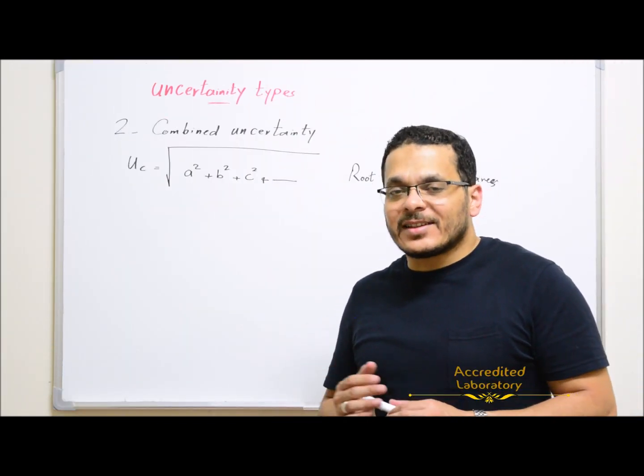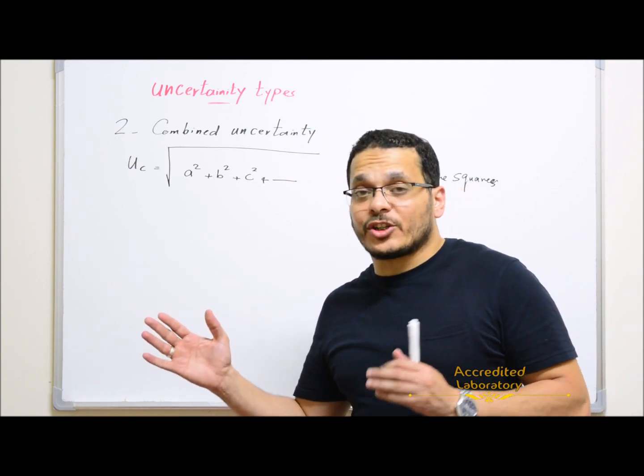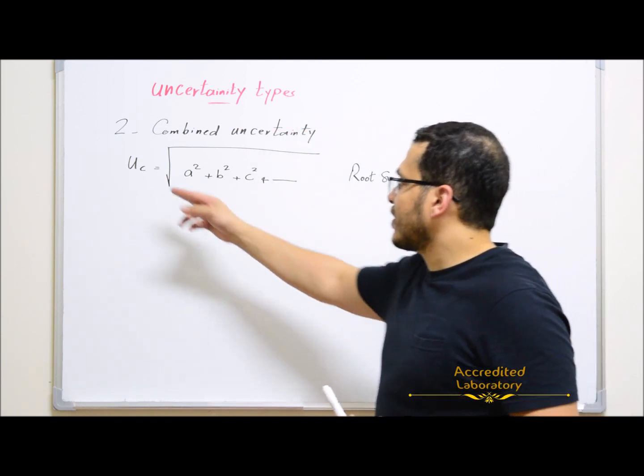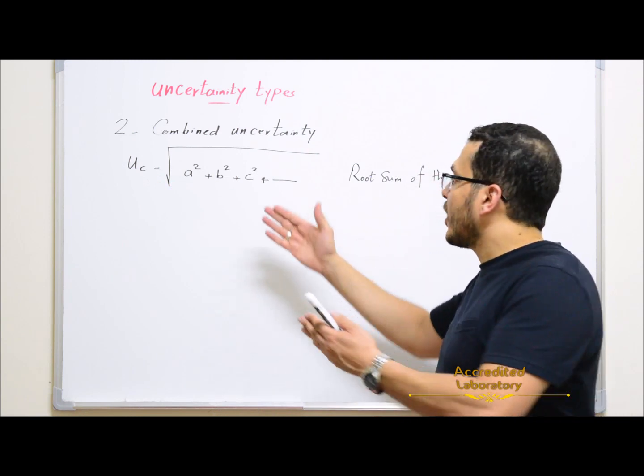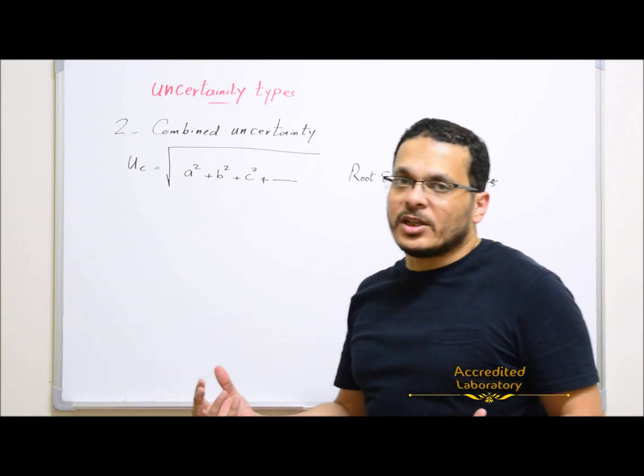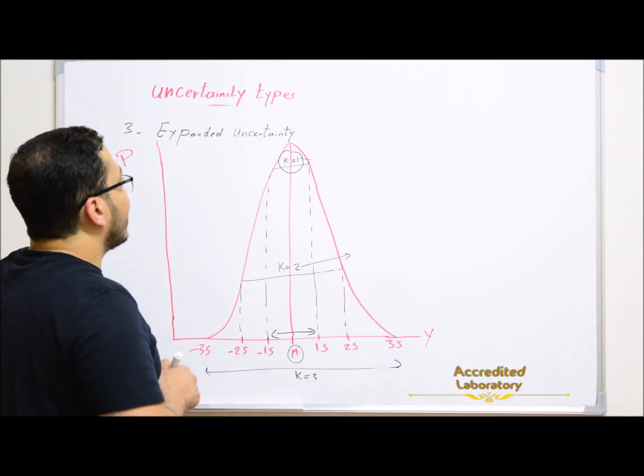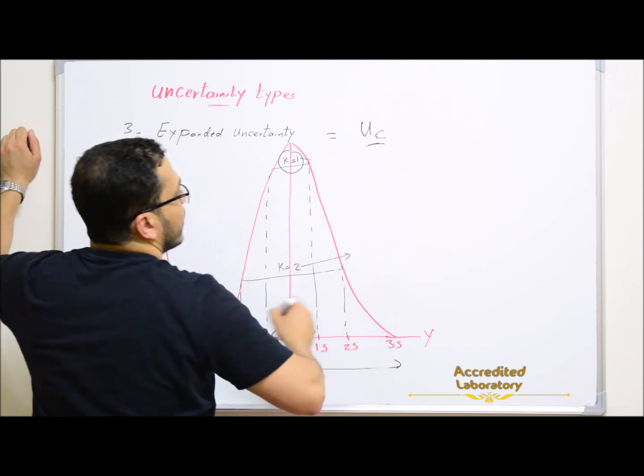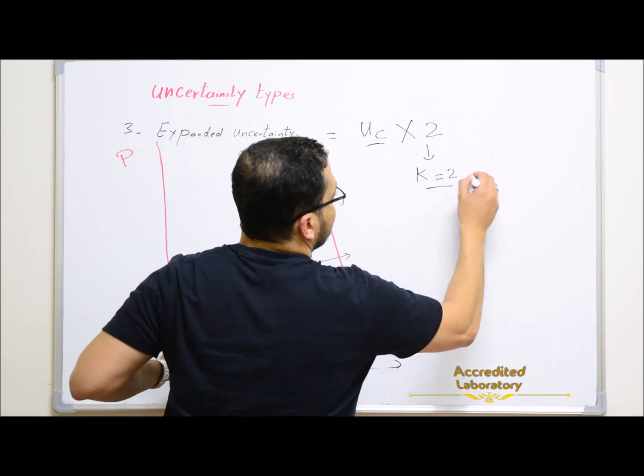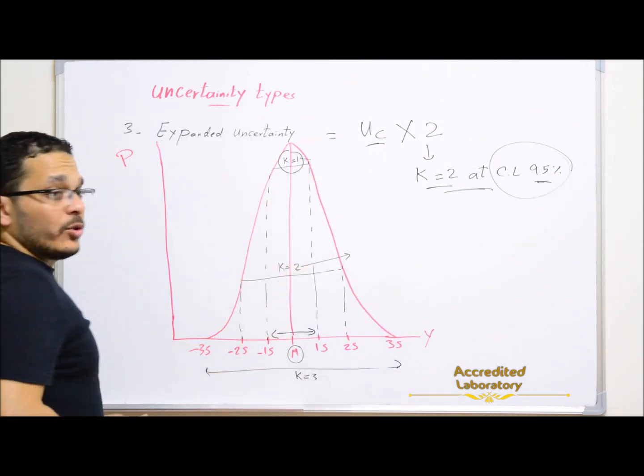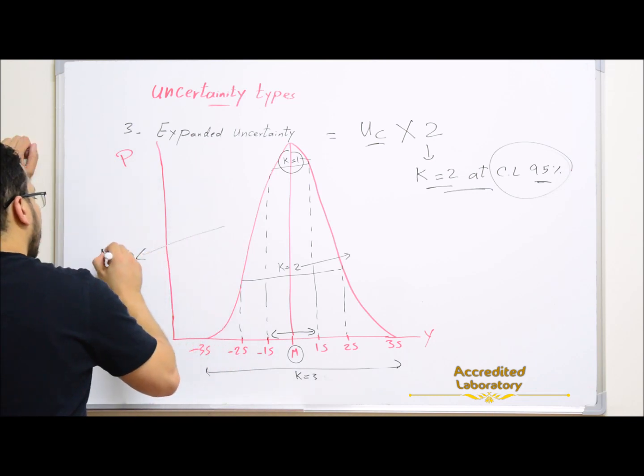After the individual standard uncertainties are calculated by Type A or Type B evaluation, they are combined together to get combined uncertainty, which is equal to the root sum of squares of all individual uncertainties. At the end, expanded uncertainty is calculated by multiplying the combined uncertainty by 2, which is the coverage factor at confidence level 95%.